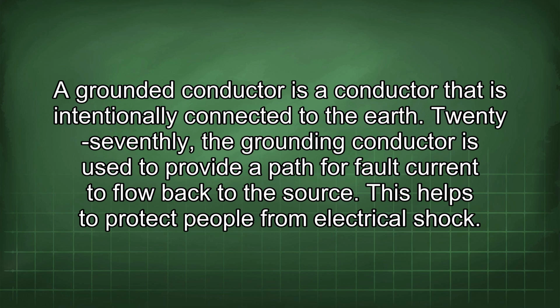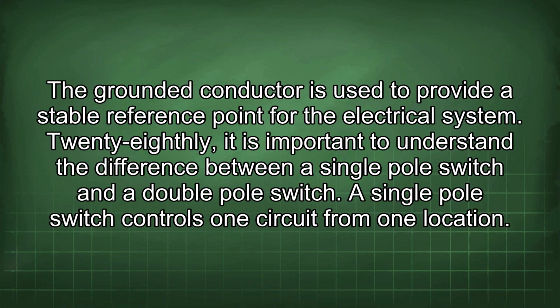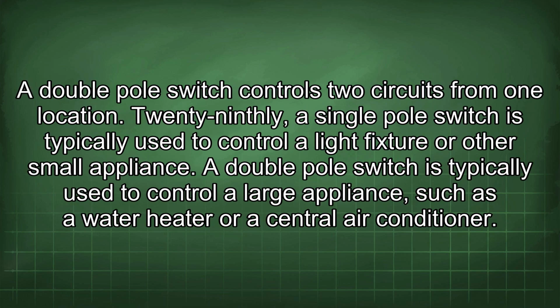Seventh, the grounding conductor is used to provide a path for fault current to flow back to the source. This helps to protect people from electrical shock. The grounded conductor is used to provide a stable reference point for the electrical system. Eighth, it is important to understand the difference between a single pole switch and a double pole switch. A single pole switch controls one circuit from one location. A double pole switch controls two circuits from one location.